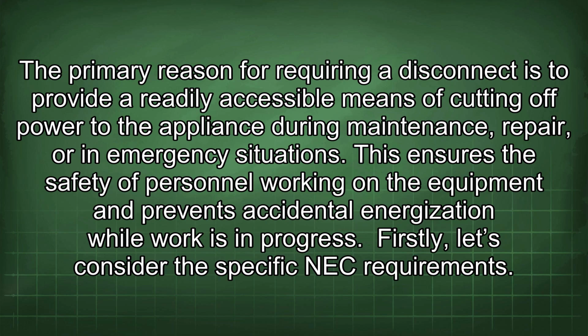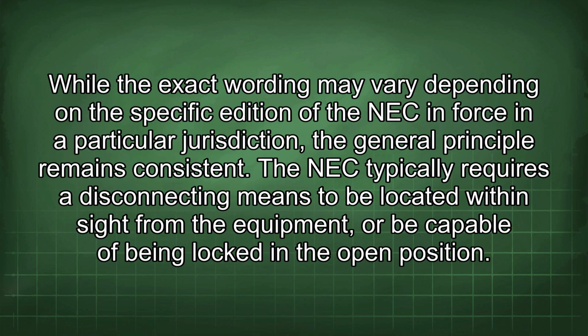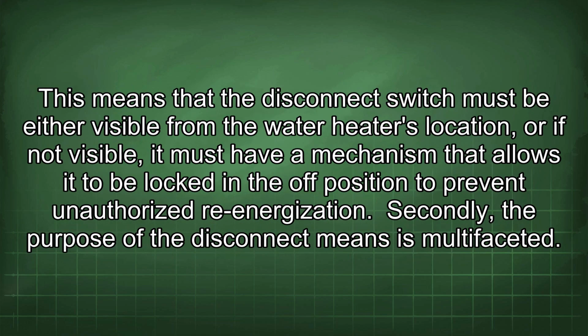Firstly, let's consider the specific NEC requirements. While the exact wording may vary depending on the specific edition of the NEC in force in a particular jurisdiction, the general principle remains consistent. The NEC typically requires a disconnecting means to be located within sight from the equipment, or be capable of being locked in the open position. This means that the disconnect switch must be either visible from the water heater's location, or if not visible, it must have a mechanism that allows it to be locked in the off position to prevent unauthorized re-energization.